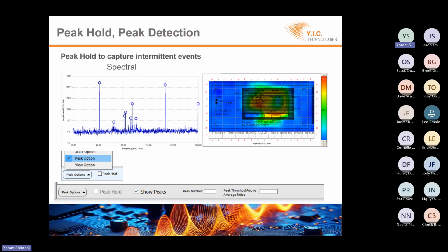But intermittent events are very, very challenging, specifically if you don't have any other means to capture or to trigger on them. You don't know the exact level. The pulse is too short to trigger either the scope, the oscilloscope, or the spectrum analyzer. So sometimes it's a real issue. You do see that in the behavior of the DUT, but it's very, very difficult to capture and understand where they are coming from. And from our experience, the best way to do that is just to have automated software that can support peak hold and continuous run. And eventually you leave it running for a minute, 5 minutes, half an hour. Eventually you will capture that event.